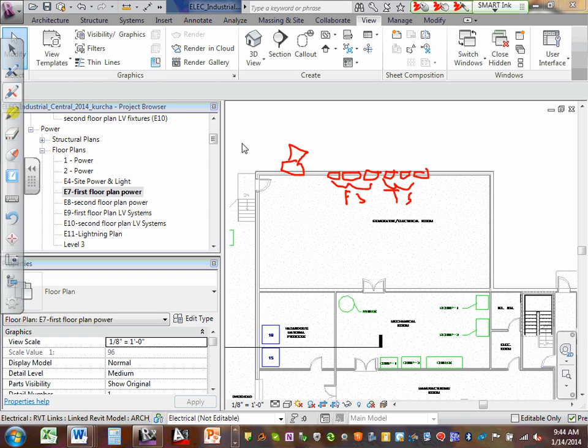And tamper switches are a supervisory device, essentially, that monitors the position of the valves on the sprinkler system. Anywhere you can turn off the water in the sprinkler system, whether it be at the main entrance or on one of, again, the zones or sections of the sprinkler system, there's usually what's called a gate valve. And the gate valve will have a tamper switch on it, so that when that valve is closed, the tamper switch closes and it sends a signal to the fire alarm system. You're required by code to monitor both flow switches and tamper switches.